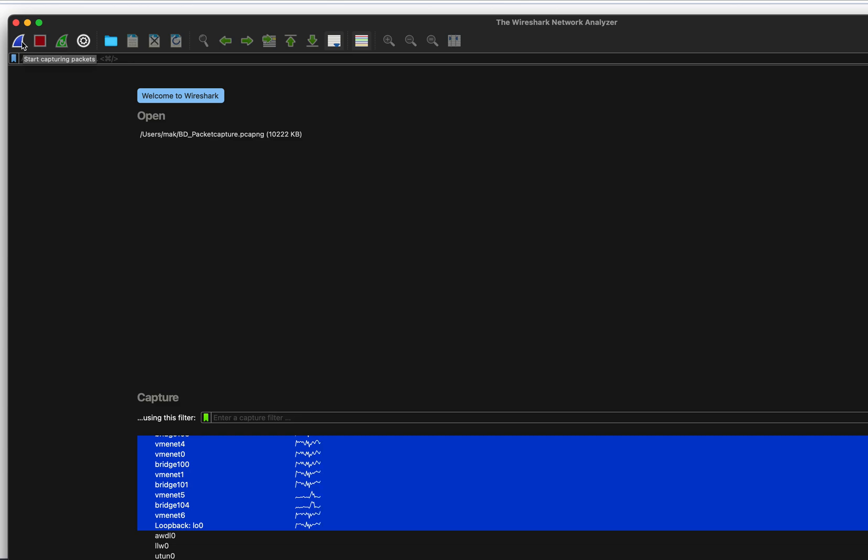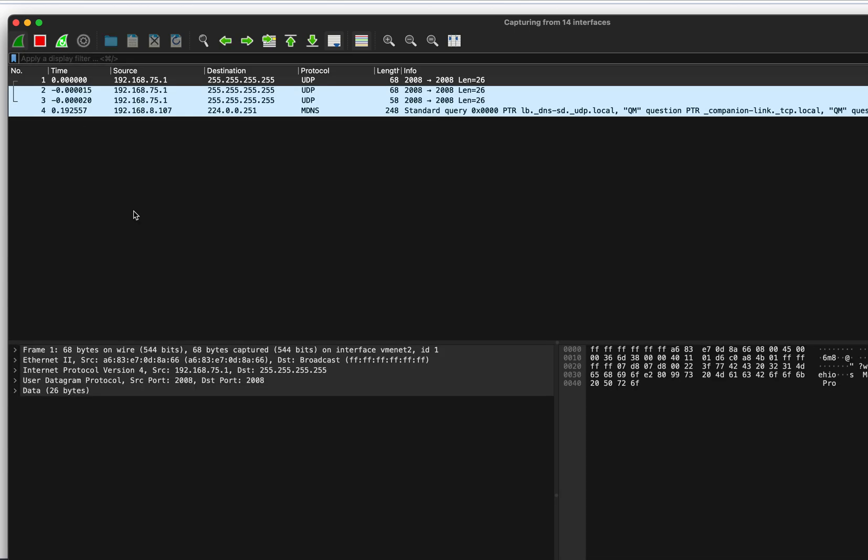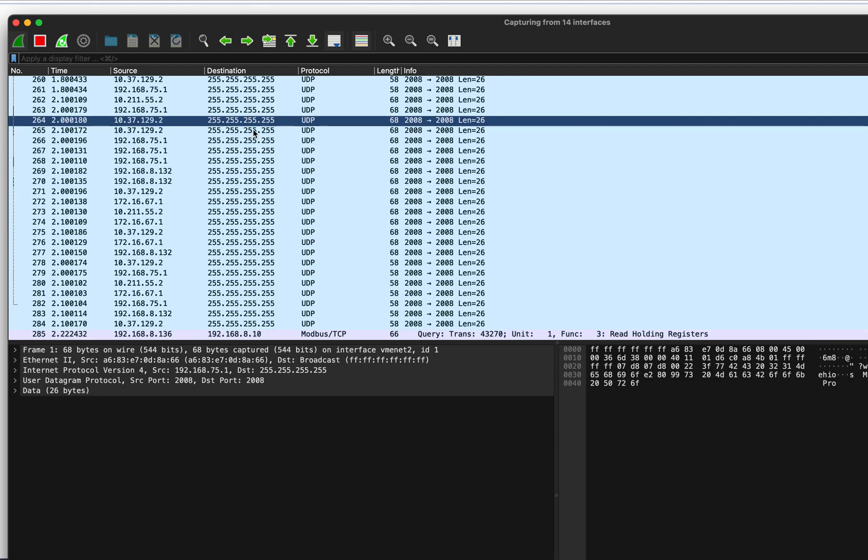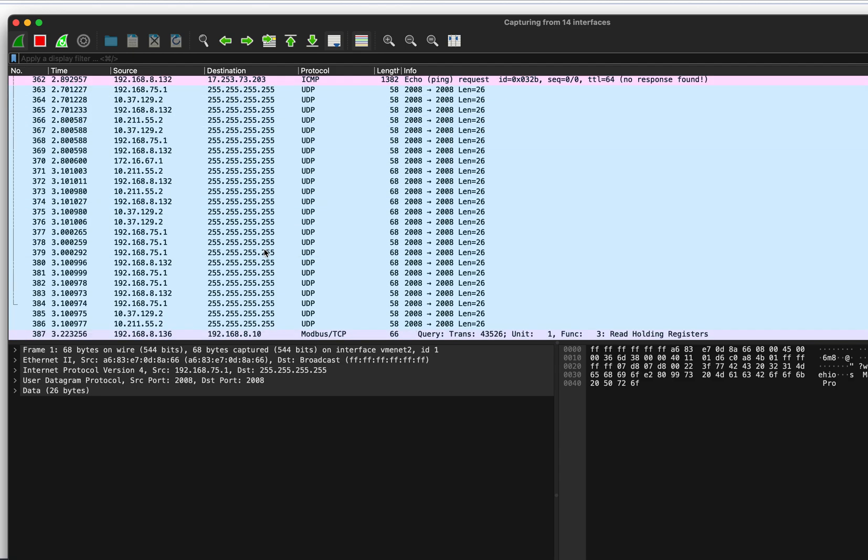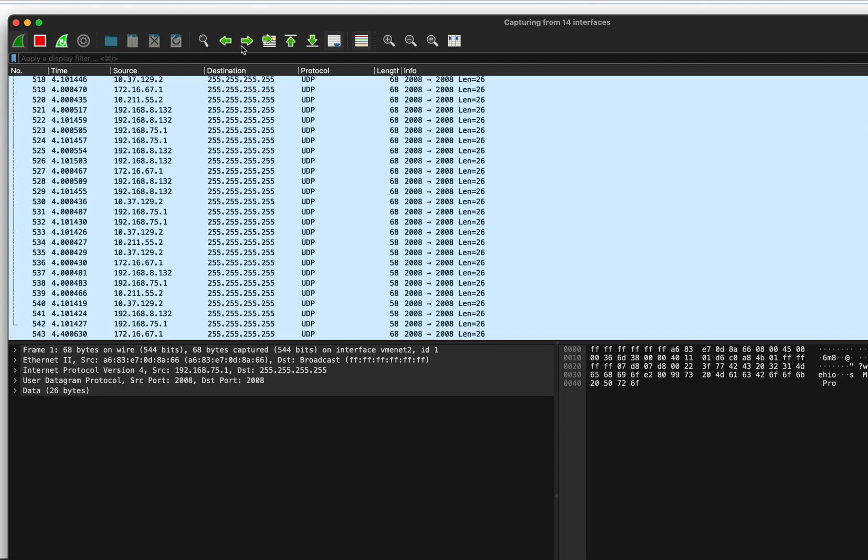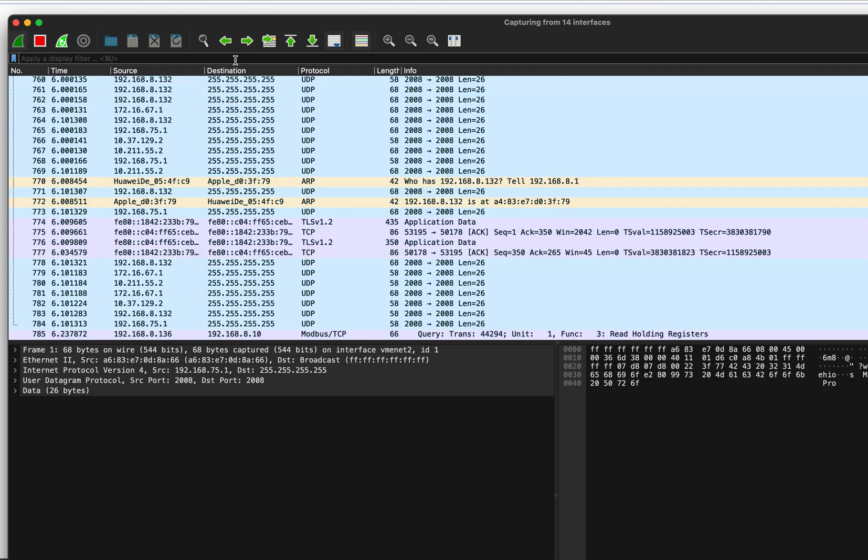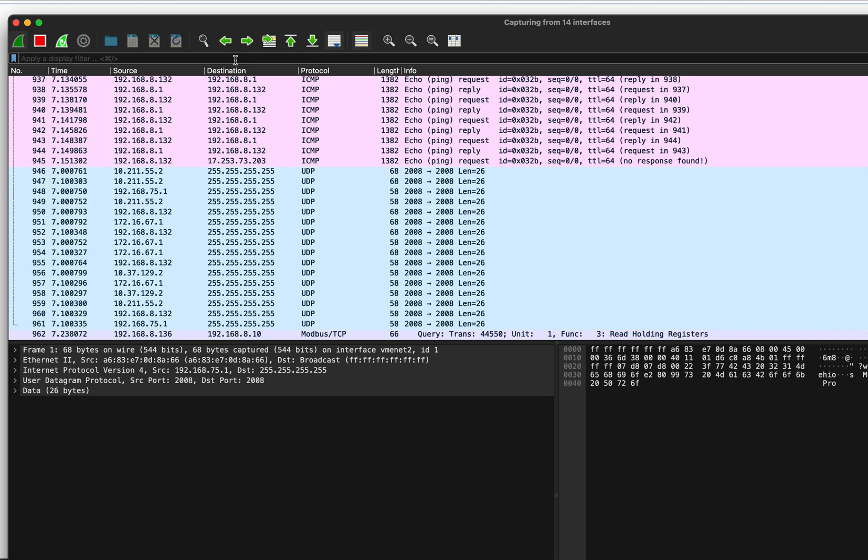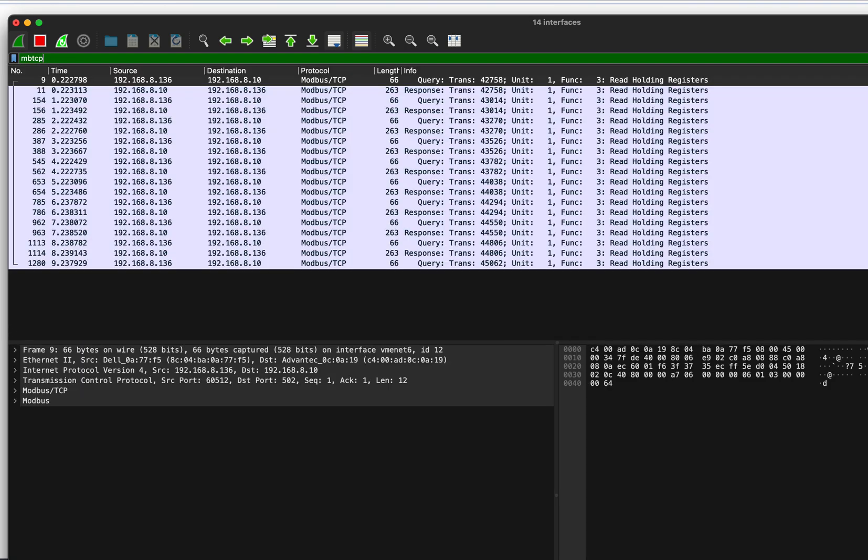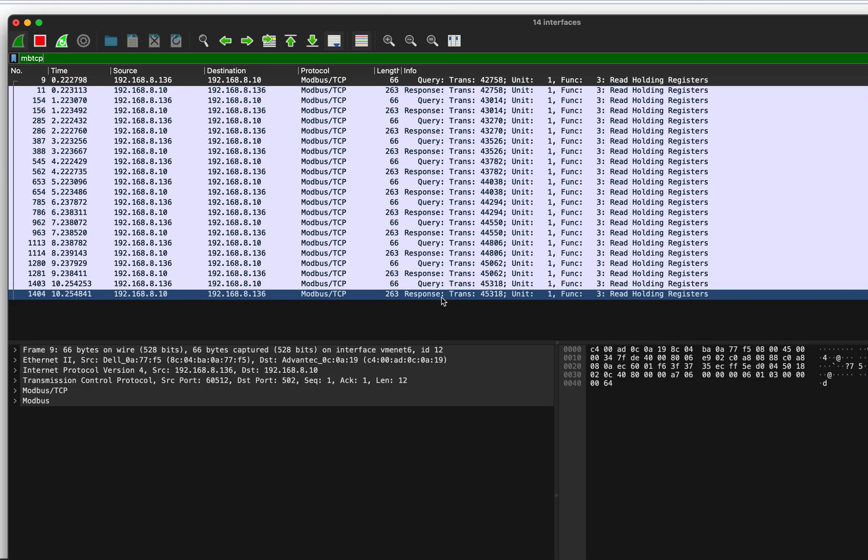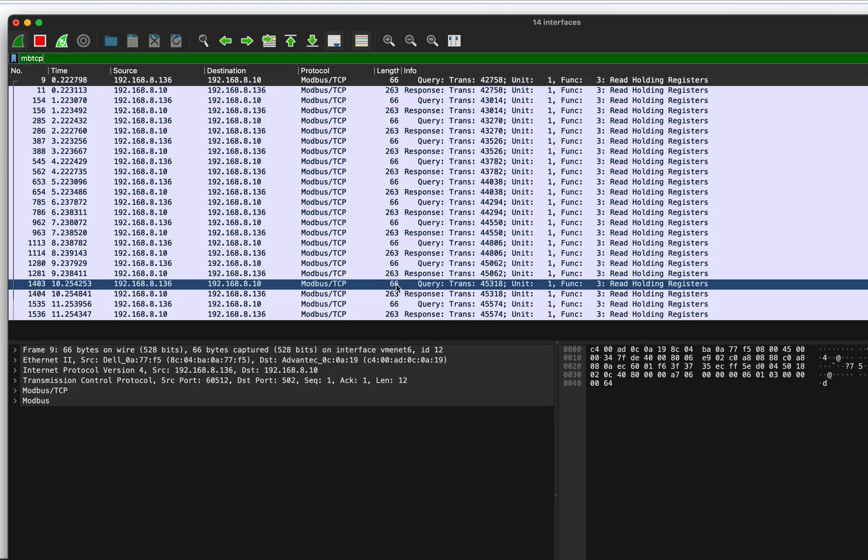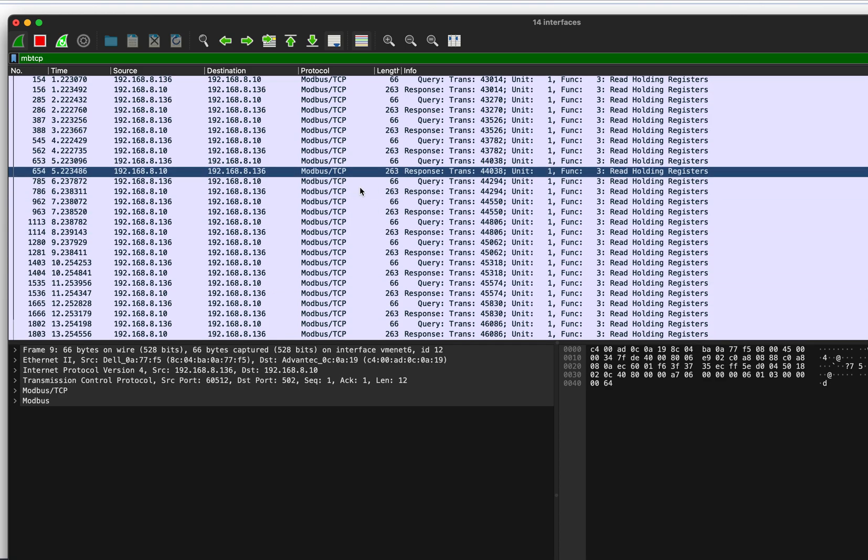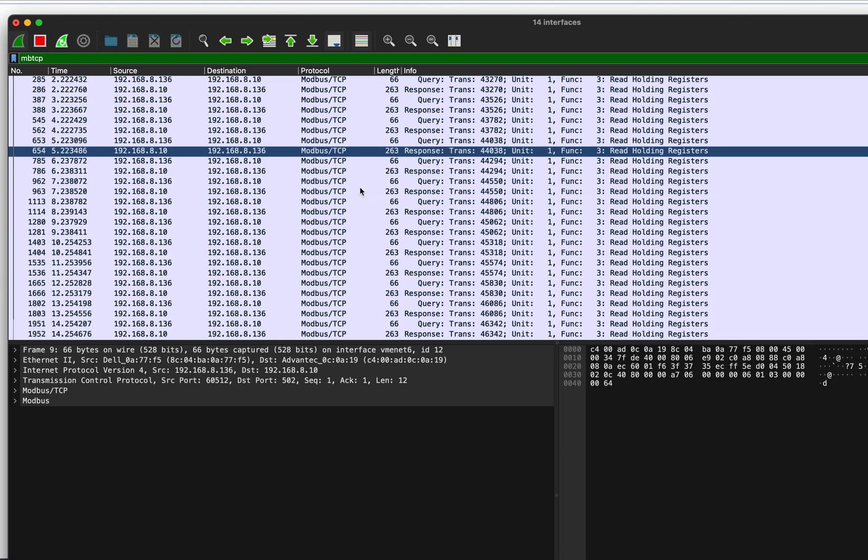Once you click on the capture button, it's going to capture everything on that network, right? UDP, TCP, everything. We don't need all that. All we need is modbus. So we're going to write MBTCP, enter, and voila!